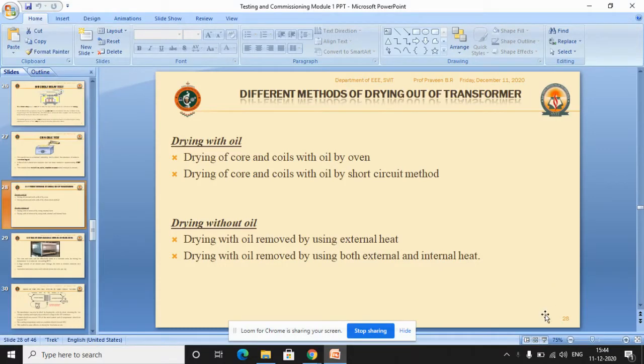Out the transformer. There are different methods of drying out the transformer. Why should you dry the windings in a transformer? Because there is a moisture content present in the transformer, and this moisture will hinder the insulation resistance. Therefore, you have to dry the moisture content that is present in the transformer windings. There are two methods of drying it.